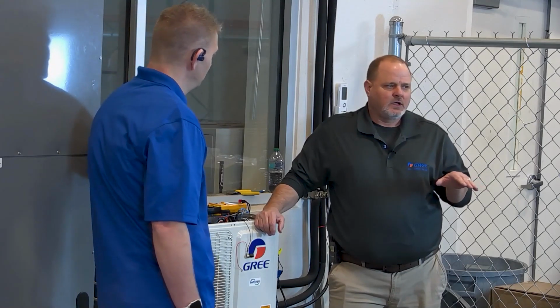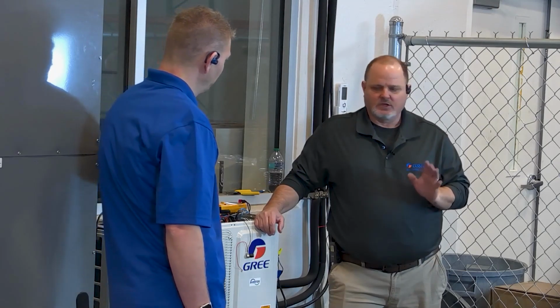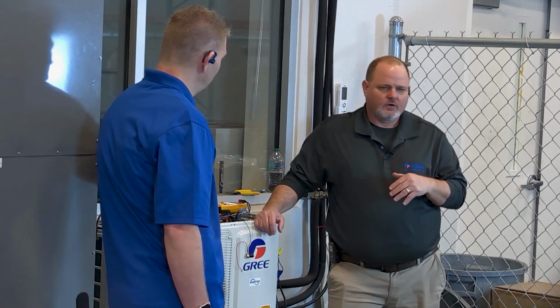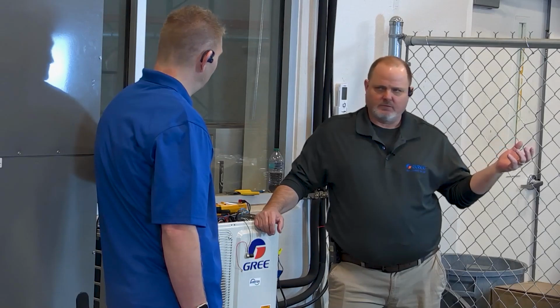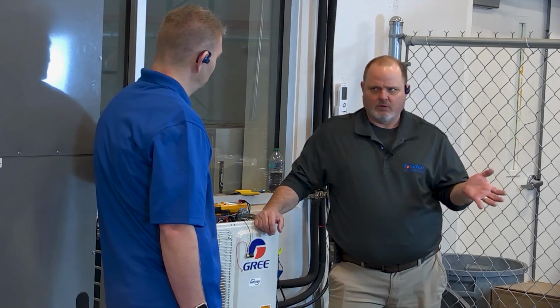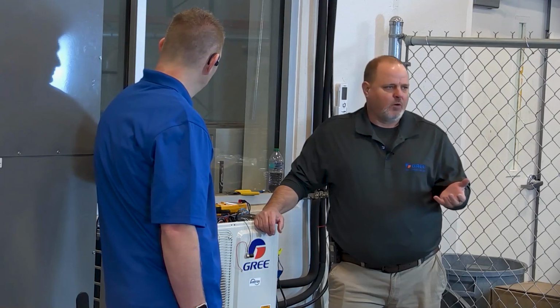Okay, so I unplugged it right away, guys, because I want you to understand that all you need to do is see if the machine will run. If the machine will run, you need to shut it back down because you don't have an indoor coil. So all you're going to do is throw it out on an error code or something anyway. So there's really no point in doing all that. We proved our point. At this point, if I got an E6 error code on this machine, I just proved with that service tool it has nothing to do with the outdoor unit.